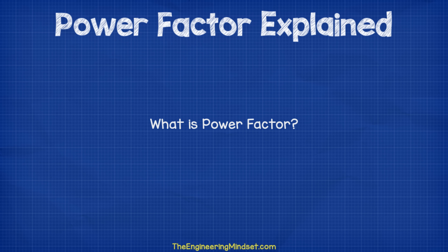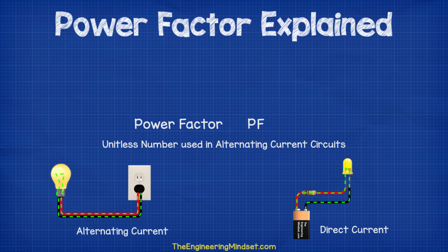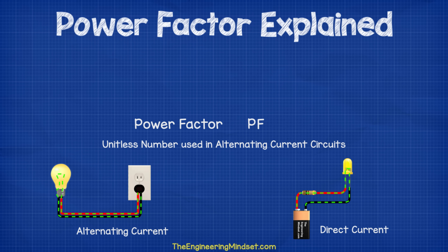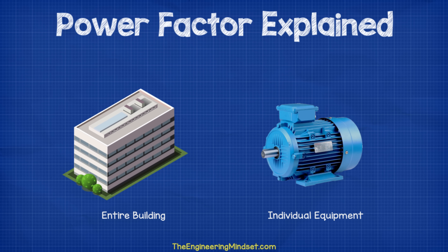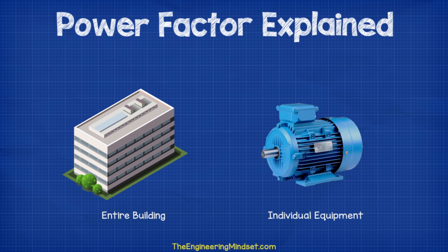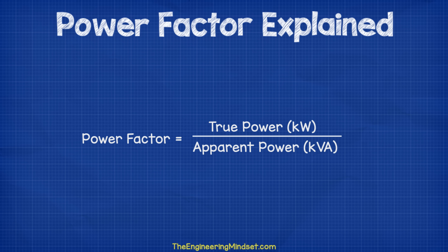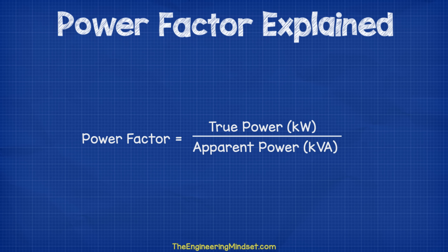So what is power factor? Power factor is a unitless number used in alternating current circuits. It can be used to refer to a single piece of equipment such as an induction motor, or for the electricity consumption of an entire building. In either case, it represents the ratio between true power and apparent power, the formula being PF equals KW divided by KVA.